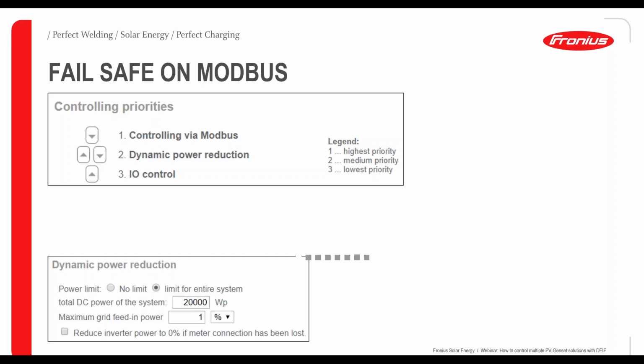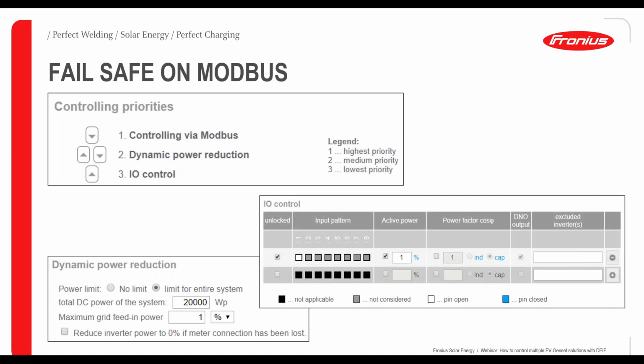So to make sure to not produce too much power in case the diesel generator would run on an inefficient level or would be in a dangerous level of running. The second option which we can set would be the I/O control. So this is also on the web UI which we can set. So here you as installer, you can decide, do I prefer dynamic power reduction or I/O control. Here we can also set an active power to 1%. So if the Modbus communication is lost, we again would only run on 1% of the maximum power we set earlier.